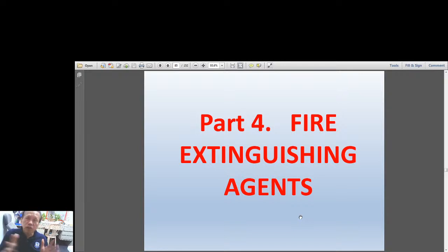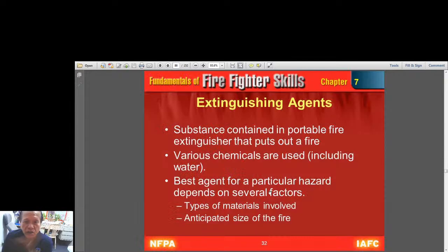So after we talk of the fire exits, we talk of the smoke detection and heat detection, then we talk of toxic gas detection, and then we talk of the air pressurization of the escape routes. Now we go to extinguishing means, no? So we'll start with the agents. So agents, there are so many agents available today. Of course, that's a little bit more expensive. Water is the cheapest extinguishing agent. It is readily available. Okay, extinguishing agents, substance contained in portable fire extinguishers that puts out a fire.